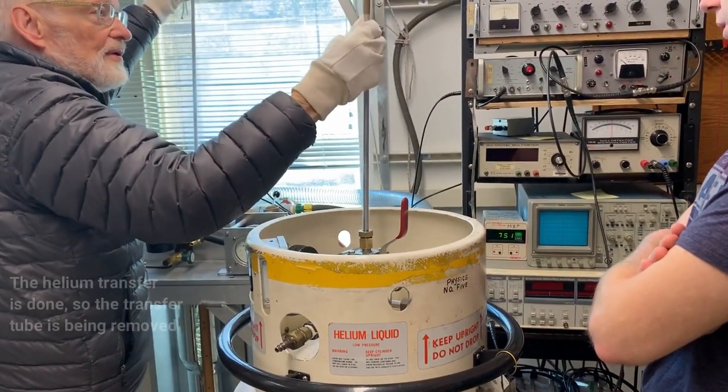It's filling faster now. You can see the nitrogen bubbles going by — it's a bit of a distraction having the nitrogen there, though you can definitely see the helium. It's almost to the liquid nitrogen level. Now it's past the nitrogen level. You might as well push it up pretty high. Tell me when it's getting just about to the middle of what we can see — I think it's there. This is where it levels itself.